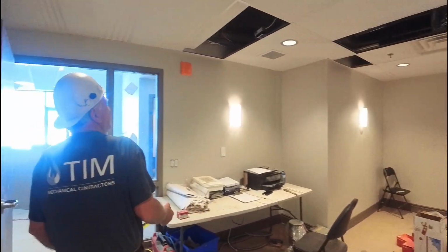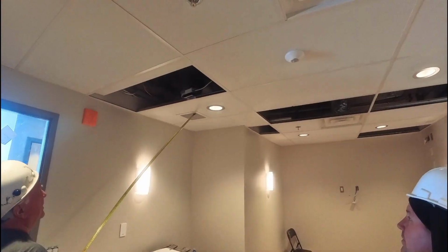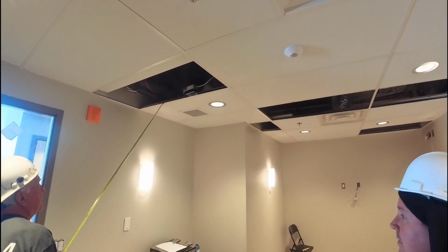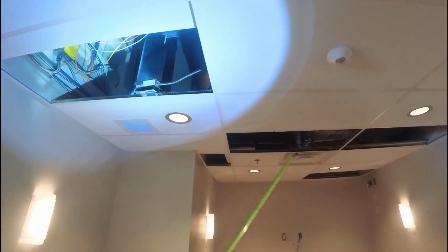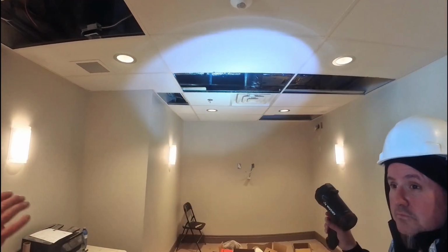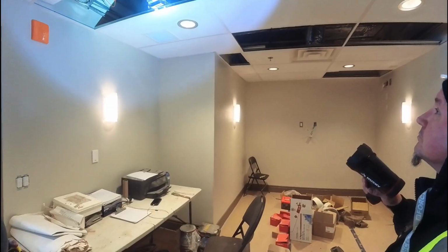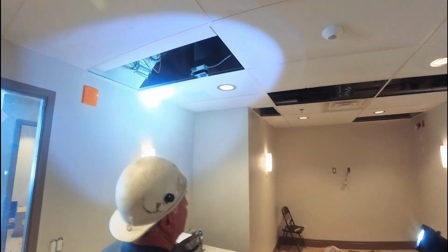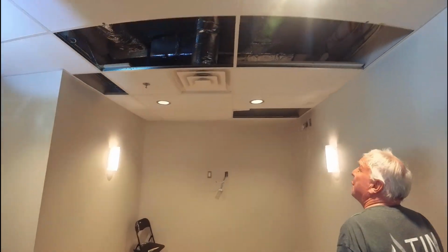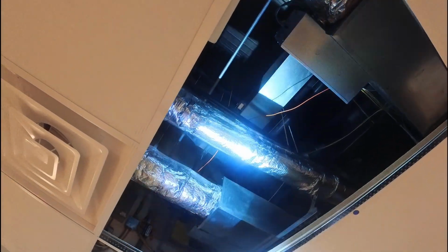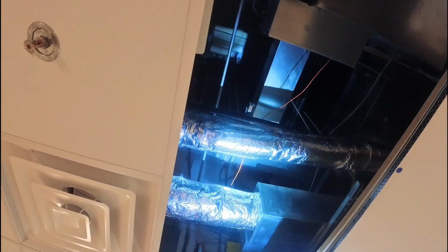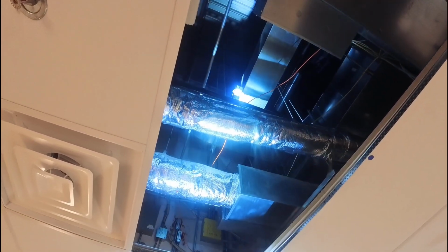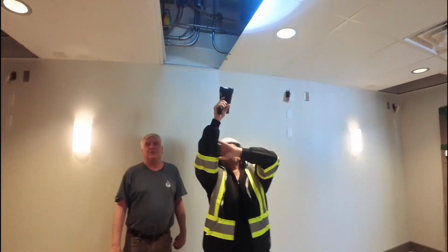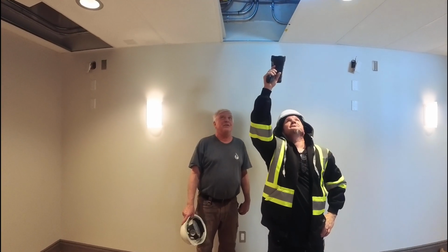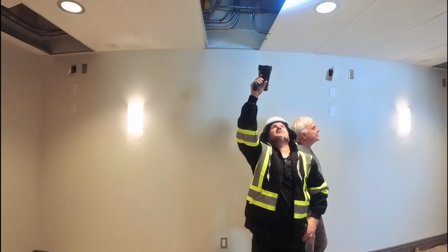Again, if you ever go to a situation where there's no exhaust going out of that, the first thing you could always do is look in there and follow it back, and see if a vibration or something has closed the volume damper. Let's follow it back right now. It's 10 by 10 ductwork, going back over this way. There it is right there, and it's in the wide open position right now. But if you came over and looked and that handle was pointing down, then you'd know there's a problem. The wing nut had loosened from vibration or something. That would be the first thing you'd look at, an easy fix to try to help out with the situation, just with airflow.